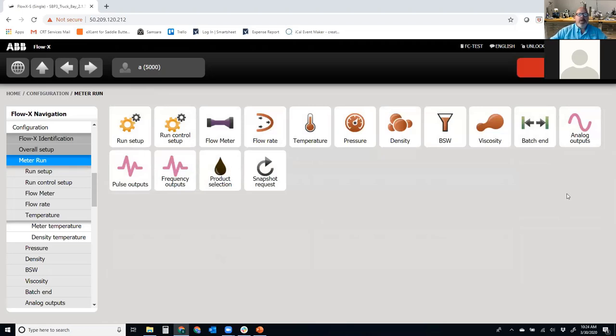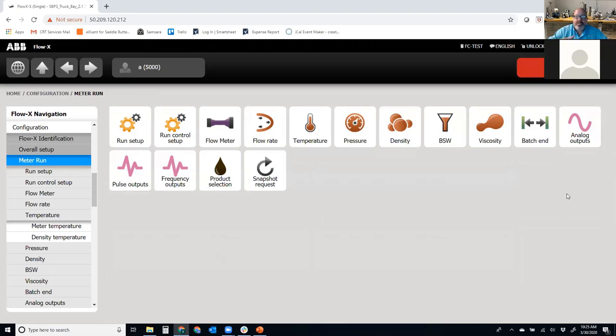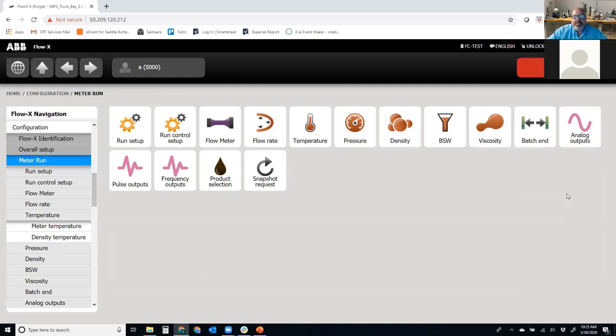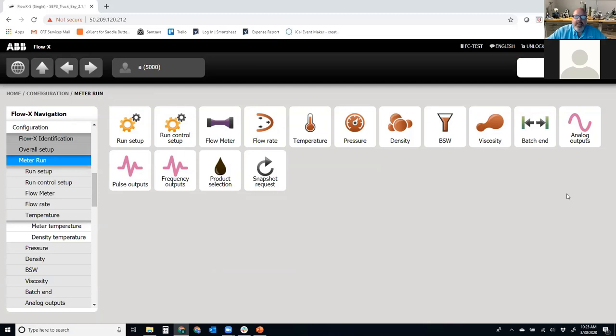A lot of different processes you can send across that analog output. The thing we have to be aware of when we set up analog inputs and outputs is if I set a scaling factor from zero to a hundred, then I need to make sure the device sending me that information is also scaled the same way. So I can make sure that on my side that four milliamps is equal to negative 50 and 20 milliamps is equal to 150.